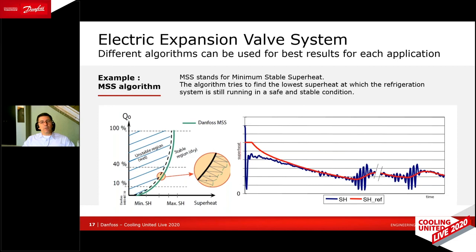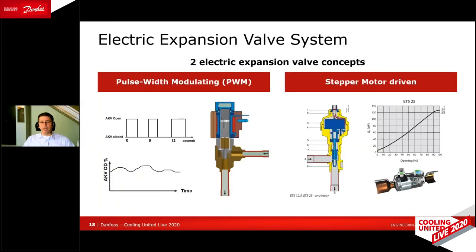This is done by the superheat controller constantly trying to reduce the superheat until it starts to become unstable. When the first droplets come out of the evaporator, the controller recognizes the superheat is too low and increases it a little, making the system stable again. After some time, it tries to reduce again — maybe conditions have changed and a lower superheat is now possible. It reduces until instability, increases slightly, waits, and tries again — always chasing the MSS curve to reach the best superheat.